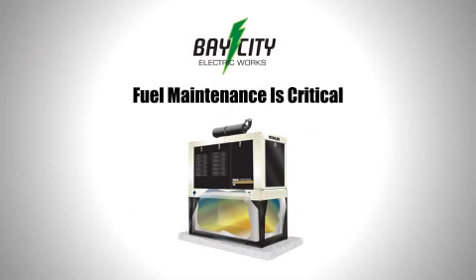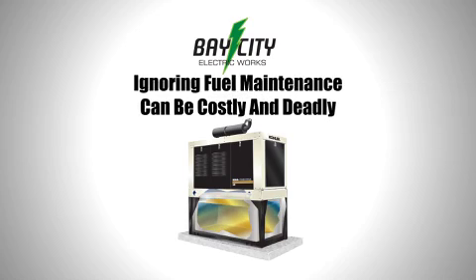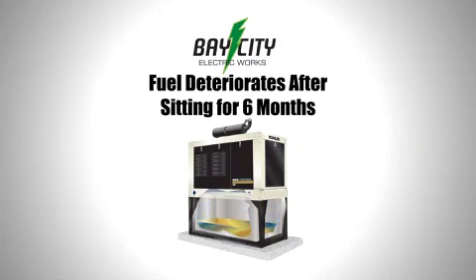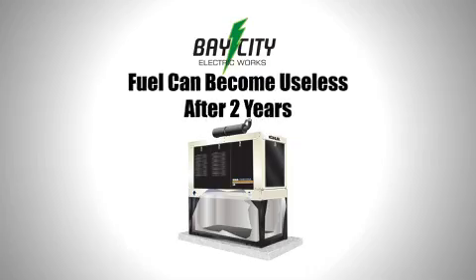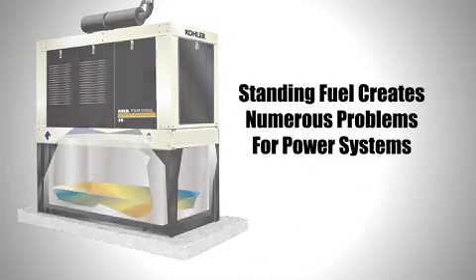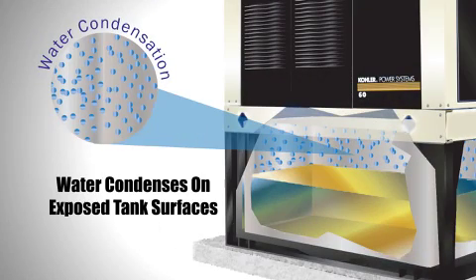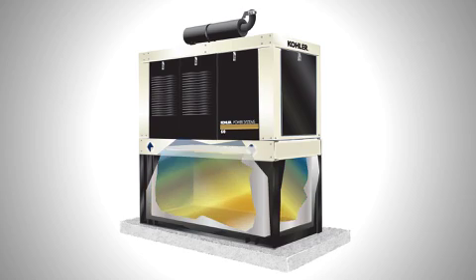One of the most common causes of failure and reduction in performance is insufficient attention paid to a system's diesel supply. Diesel left standing for extended periods degrades substantially to the point of becoming totally useless. Standby power systems are particularly susceptible to diesel fuel issues because their fuel source is left standing for several months. Diesel is particularly susceptible to degradation by water, which can further degrade the fuel and increase sediment accumulation in the base that can be sucked into the engine's fuel delivery system. If nothing else, a diesel tank should be kept full.